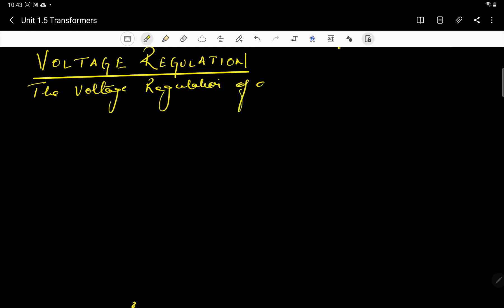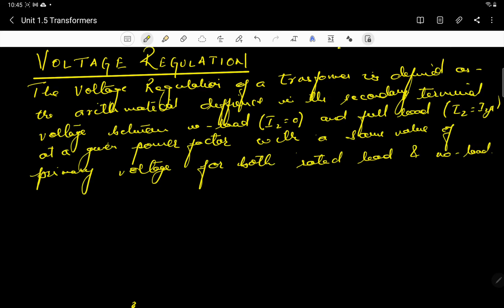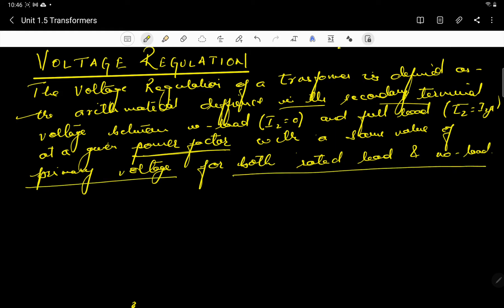The voltage regulation of a transformer is defined as the mathematical difference in the secondary terminal voltage between no load — when current is zero — and full load — when the full current is passing through the circuit — at a given power factor. The power factor should be given with the same value of primary voltage for both rated load and no load.